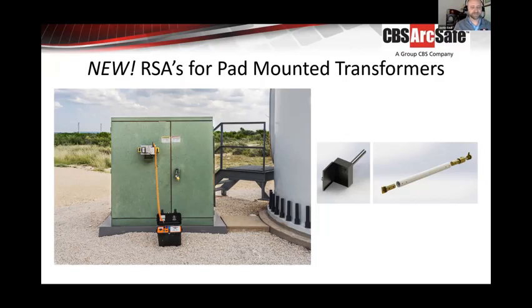So we designed a solution where you install a door port on the outside of the transformer. There's a hot stick that goes back and interfaces with the switch in the transformer, and then our motorized switching device attaches magnetically to the outside of the transformer and operates the switch inside. Then the technician can stand around the side of the wind tower or 100 feet away and operate it using wireless controls. So we have some companies putting these on their pad mount transformers out on wind farms. We've had some success with this as well in solar applications. So that's an exciting new area to do some work for transformers.